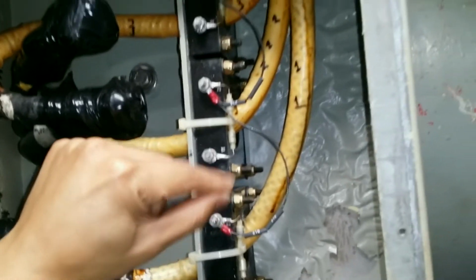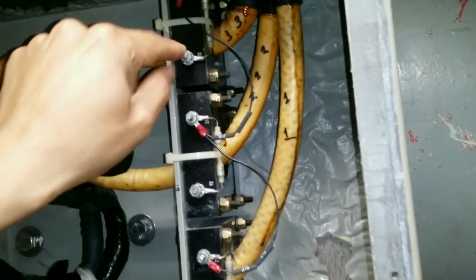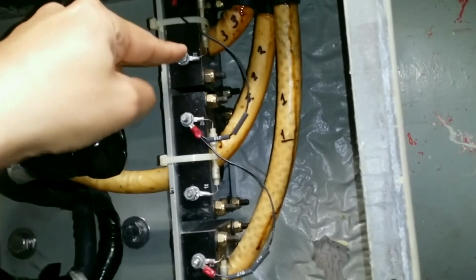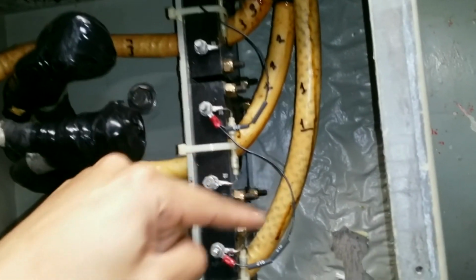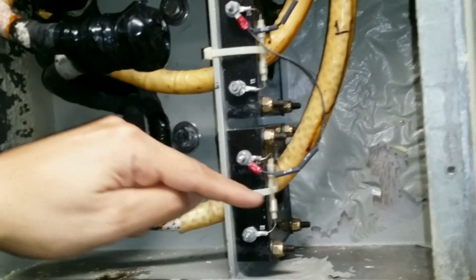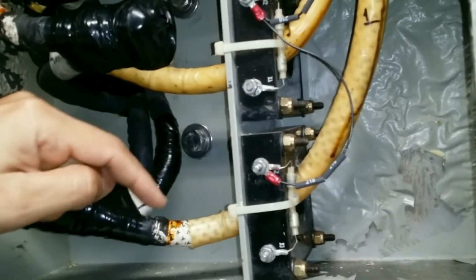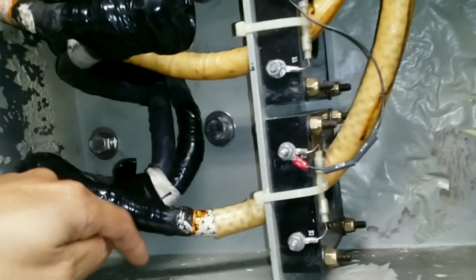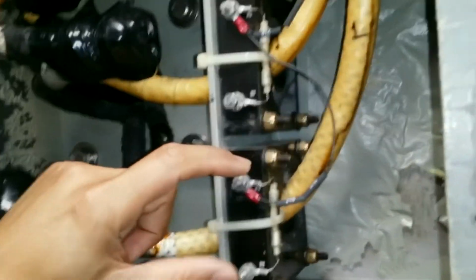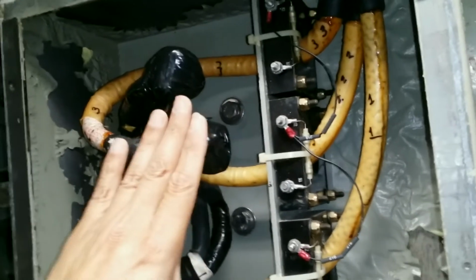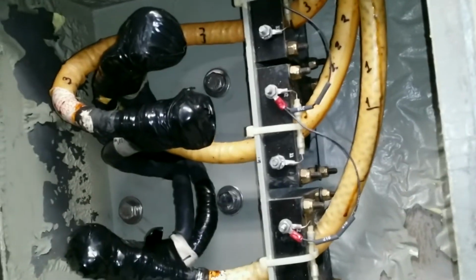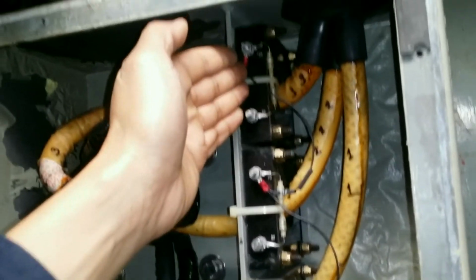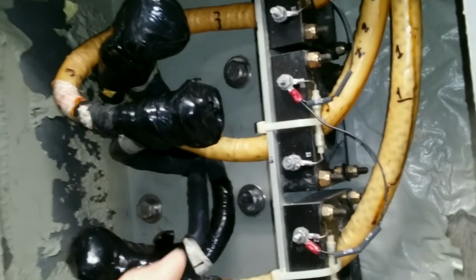These are connected in Y, and this will be Charlie, this will be the output for bravo, this will be the output for alpha. There will be a multi-conductor cable that feeds to the computer. And they provide feedback of the current that is going to the motor. So if anytime you have issues with current not reading right, these guys need to be working and doing what they're supposed to be doing.